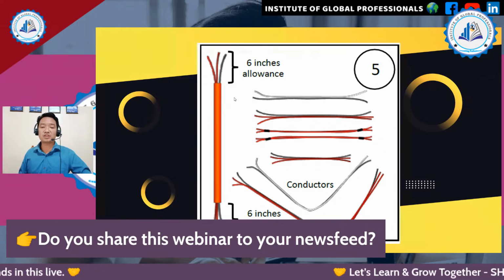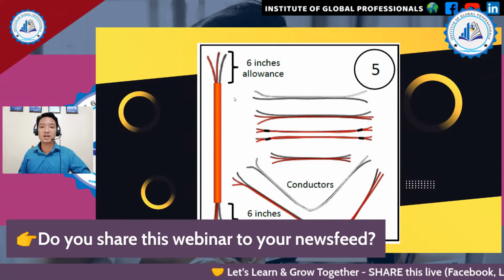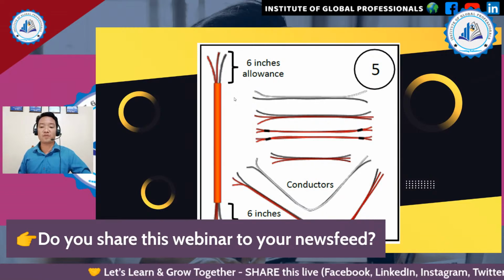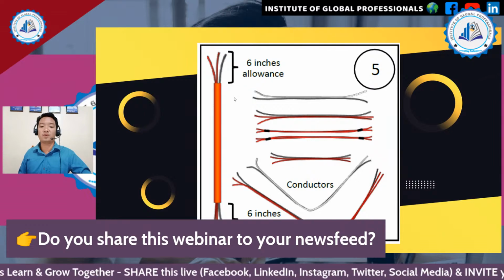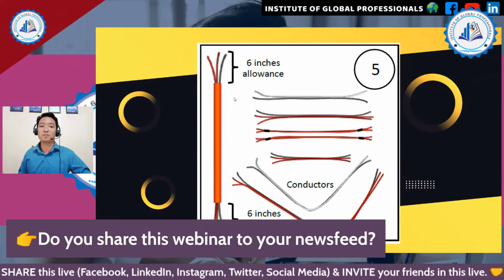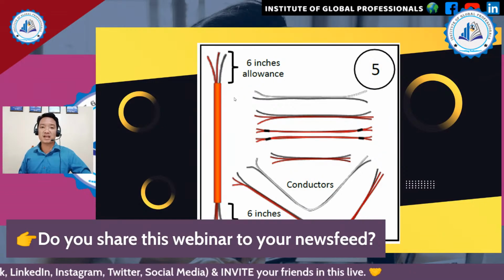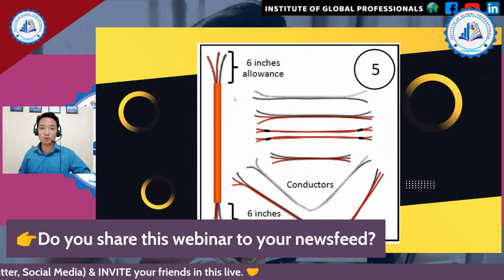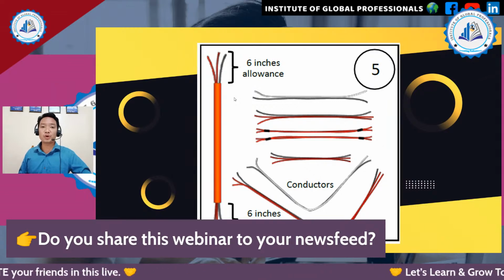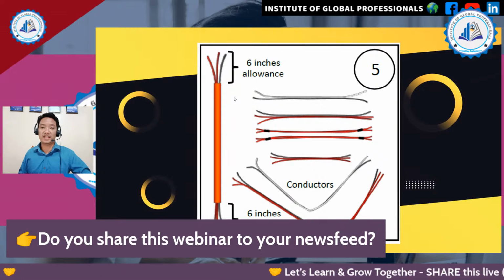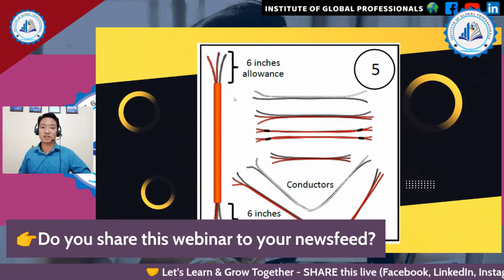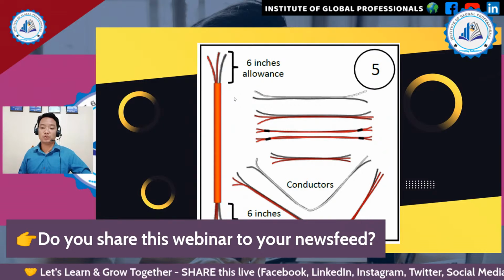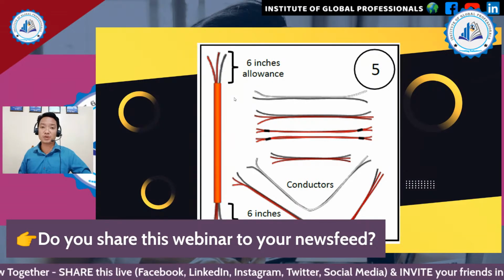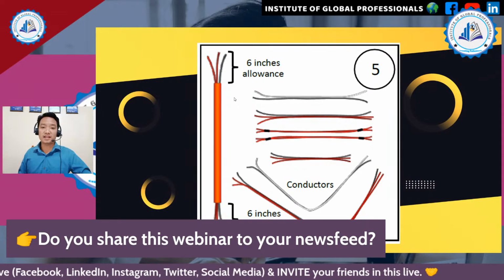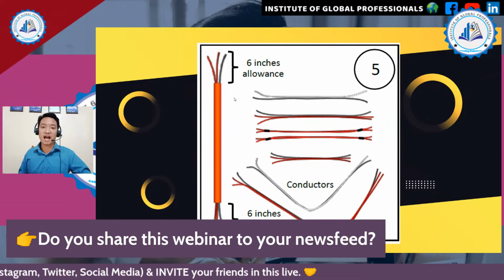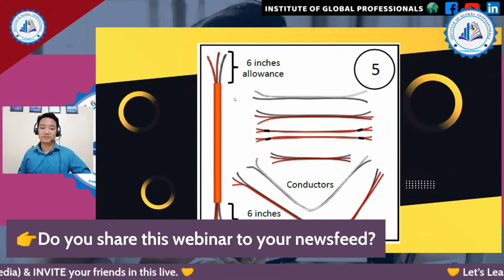And make sure that you will be having markings or tagging on the different wires if you will be using only one color of wire. For example, all black colors for neutral, hot, and ground wire, you should know how to mark each. So one for the ground, two for the neutral, and three for the hot wire. So you can use electrical tape, or you can also use colored tapes to mark what is being used for the hot, neutral, and ground wire.